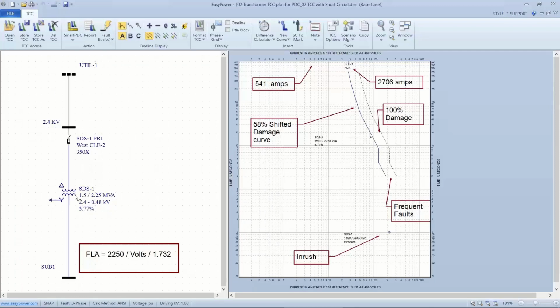So it reiterates the point of making sure the full load current is based upon the fan-cooled MVA, and so that's why we're using the 2250. The inrush and frequent fault is based upon the self-cooled ratings. Okay, so when we get into protection, we'll be making sure, one, that we're looking at the right curves, and two, we're applying the correct type of fault for that particular function. And again, the 58% derating curve is only for primary protection of a single line to ground fault in a delta Y transformer.